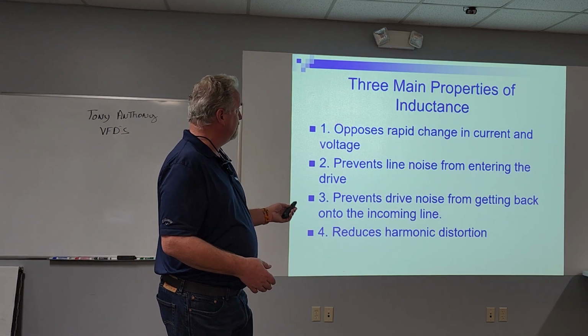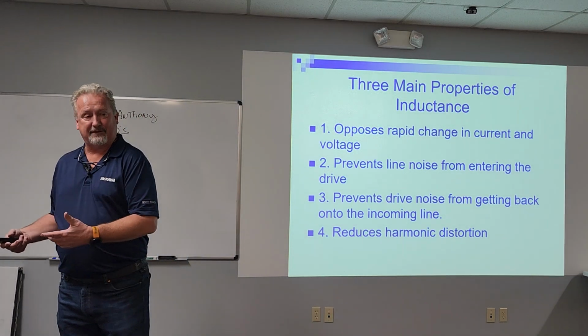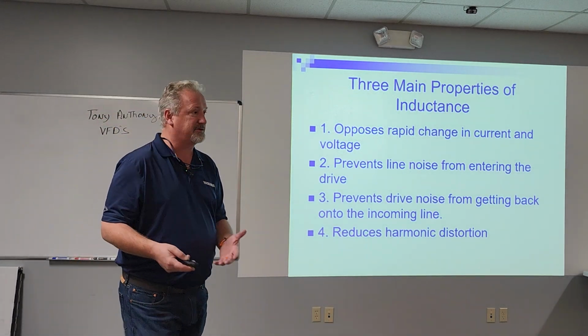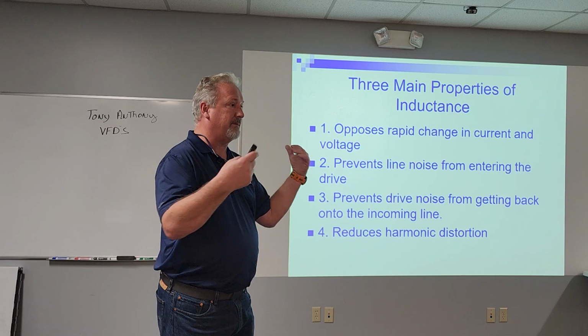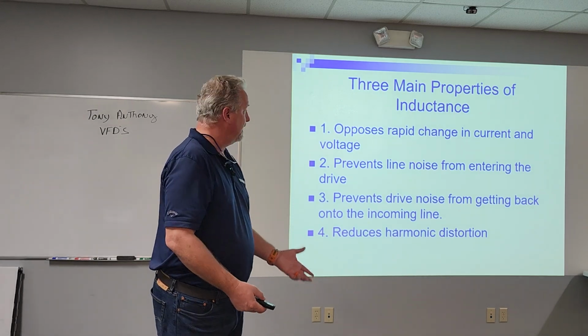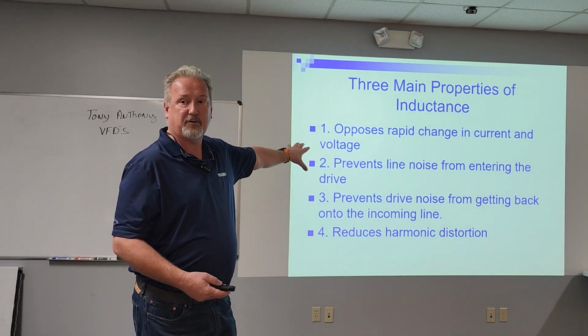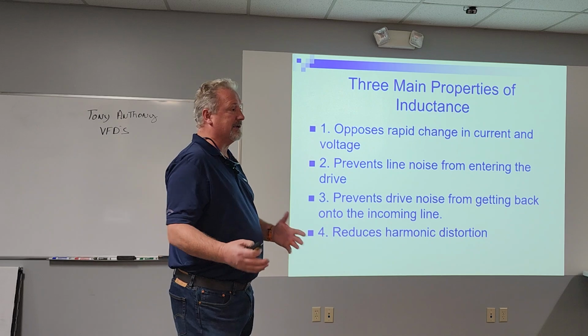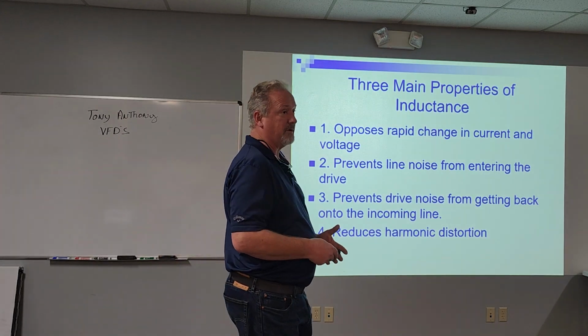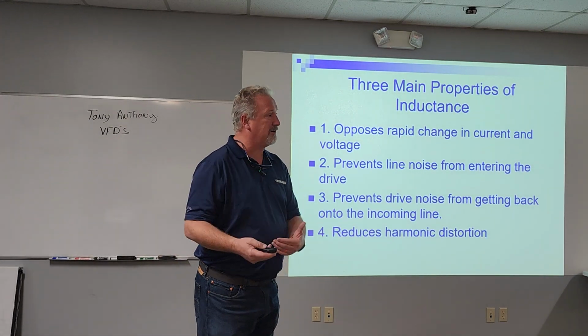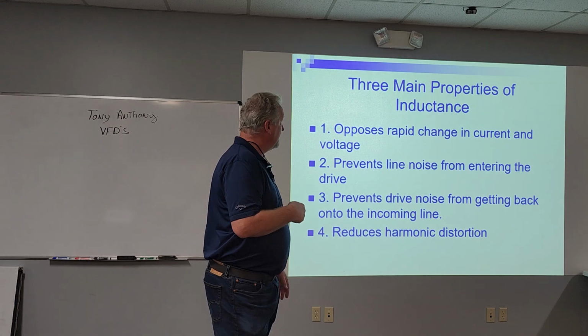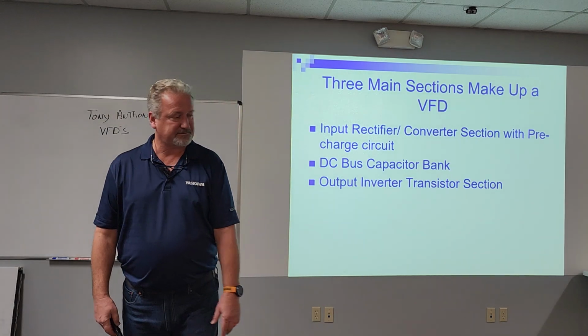All right. So really, feeding a drive, the biggest things we want to make sure of is we have short circuit protection. We have a means of disconnecting and isolating the drive. And then sometimes we may need something for harmonics. That's pretty much all we think about for feeding the drive for the most part. If you get outside of that, let's talk. We can discuss more.